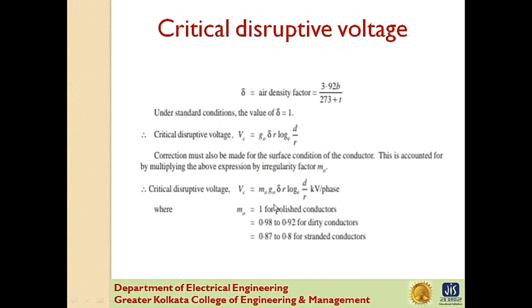Next one, visual critical voltage. It is the minimum phase neutral voltage at which corona glow appears all along the line conductors. That's why it is named visual critical voltage. The formula is: visual critical voltage equals mv, the irregularity factor, times G0, the breakdown strength of the air, times delta, the air density factor, times r, the radius, times the bracket 1 plus 0.3 over root of delta r, into log D by r, where r is the radius and D is the spacing between conductors. Again this is expressed in phase voltage.